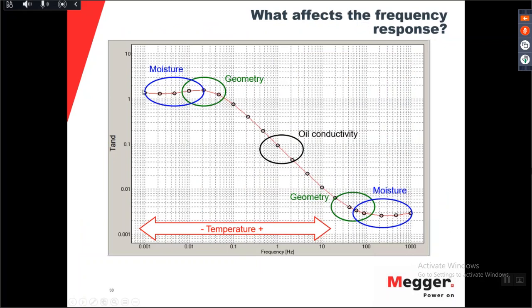When the moisture content increases, this one goes up, this one goes up. When the moisture content decreases, this one goes down, this one goes down. For the oil conductivity, this curve goes here. When it's bad, when it's good, it comes here. And then you can use this model described by the CIGRE technical brochure, and you can apply that on your measured response. And you don't need to have any previous knowledge of your transformer.